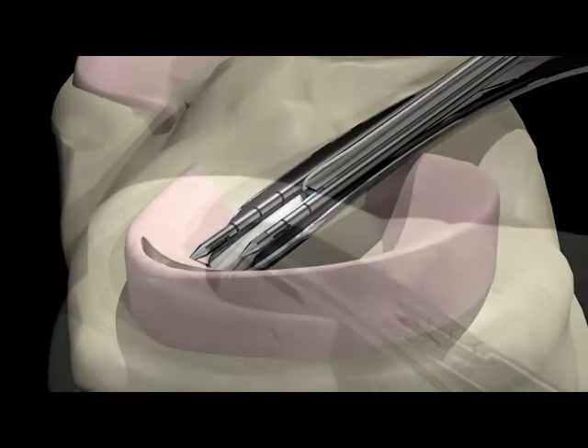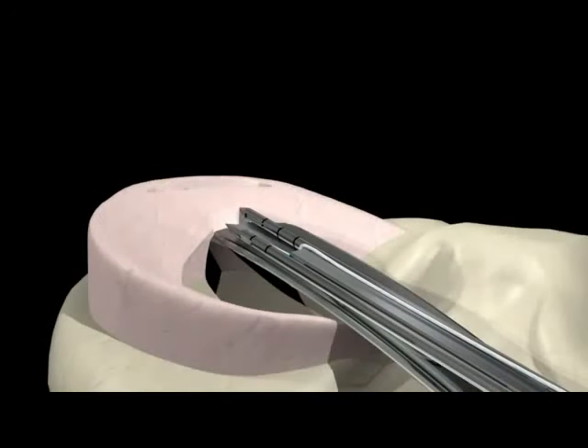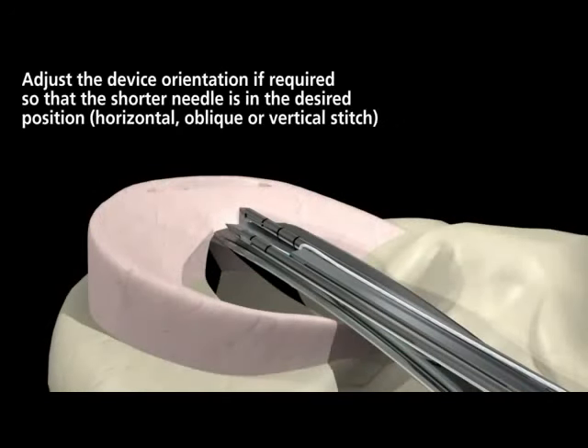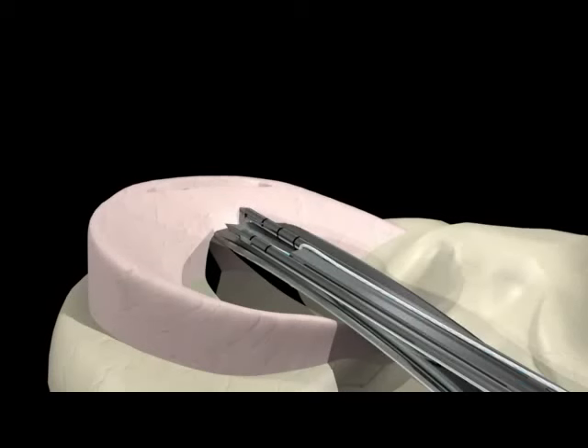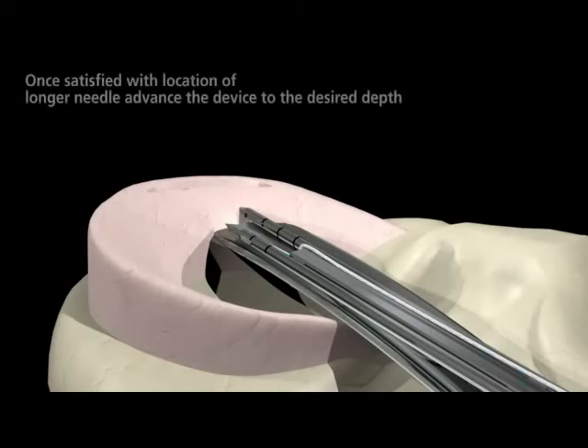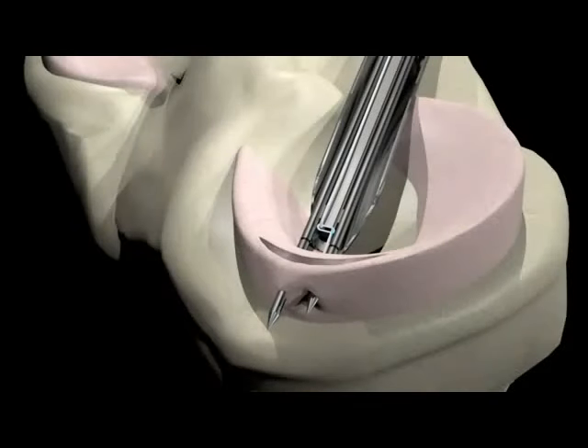Advance the longer needle until it just penetrates the meniscal tissue. Adjust the device orientation if required, so the shorter needle is positioned for a horizontal, oblique, or vertical stitch. Fully advance the needles to the desired depth. Note, the markings on the needles are at 5 mm increments, allowing for the predetermined depth of penetration found earlier.